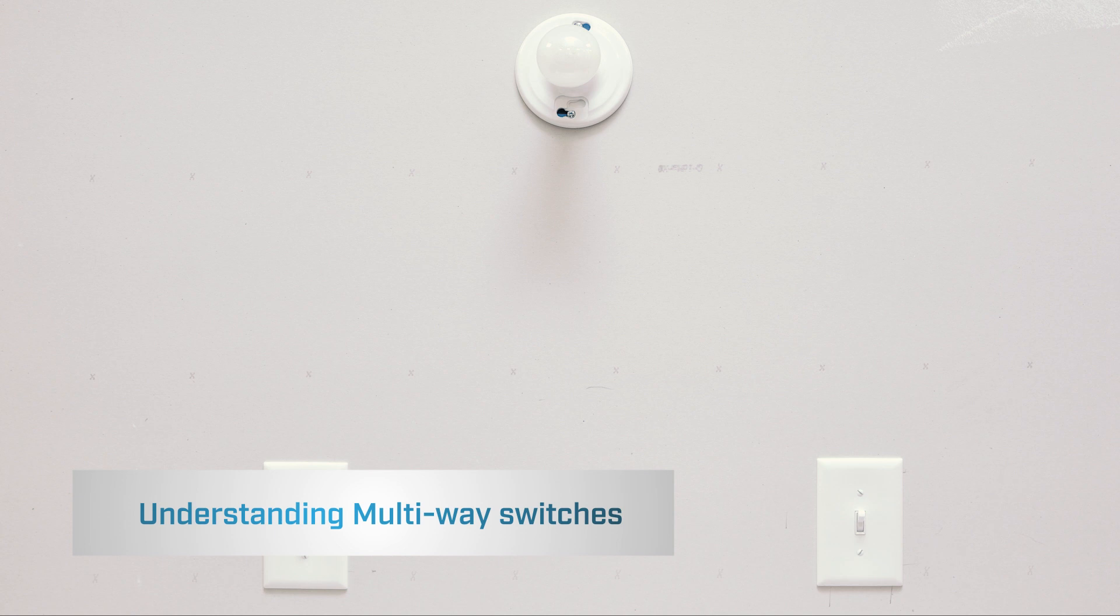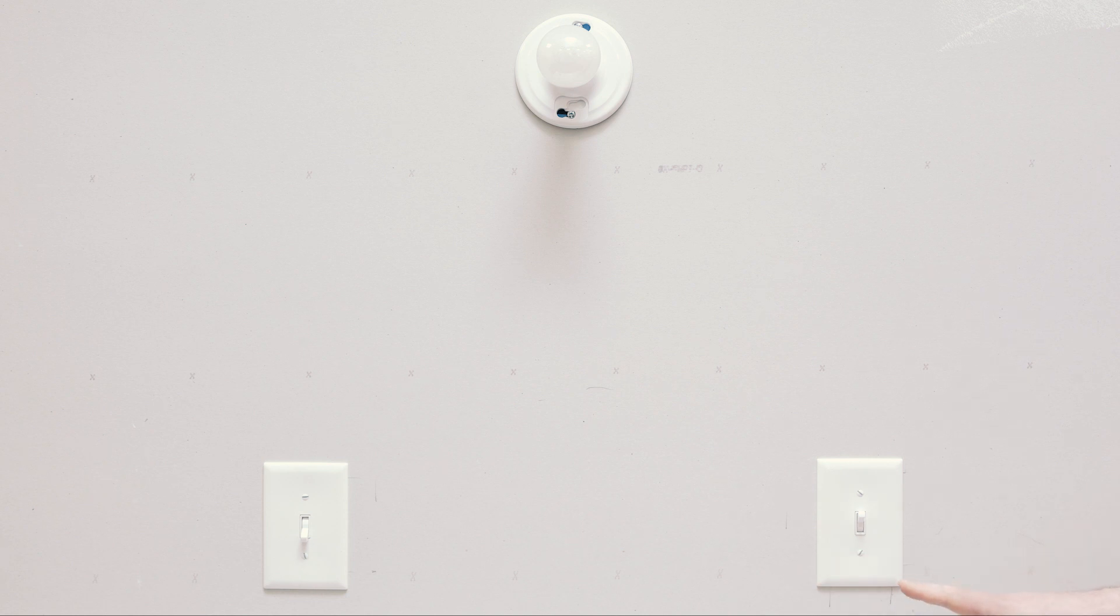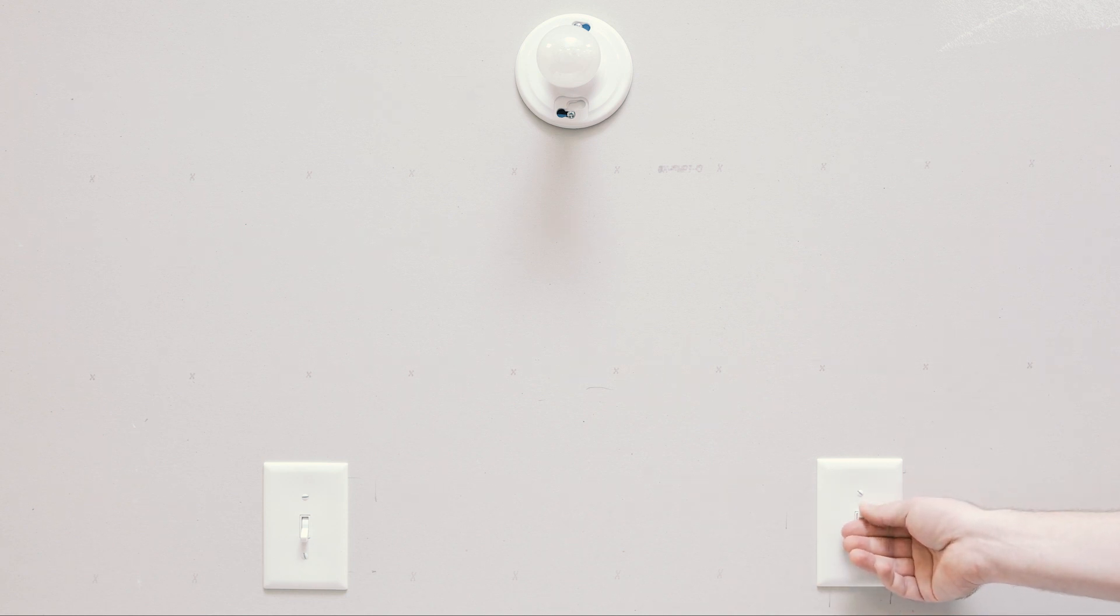The first thing you want to do is identify where the power is coming in and where the load is running to. There's two traveler wires traveling between these two locations, so we need to determine which location has the load and which has the power.